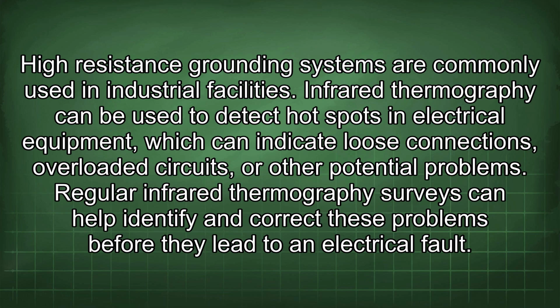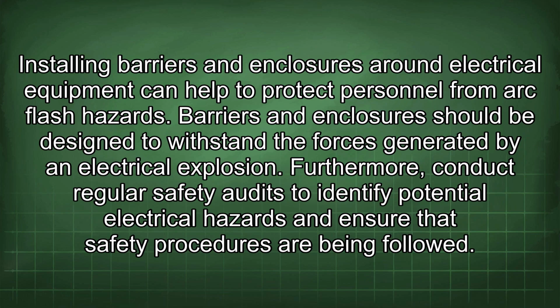Infrared thermography can be used to detect hotspots in electrical equipment, which can indicate loose connections, overloaded circuits, or other potential problems. Regular infrared thermography surveys can help identify and correct these problems before they lead to an electrical fault. Installing barriers and enclosures around electrical equipment can help to protect personnel from arc flash hazards. Barriers and enclosures should be designed to withstand the forces generated by an electrical explosion.